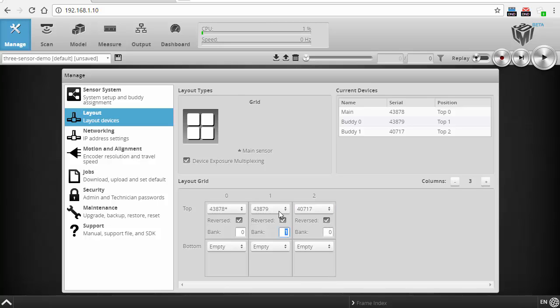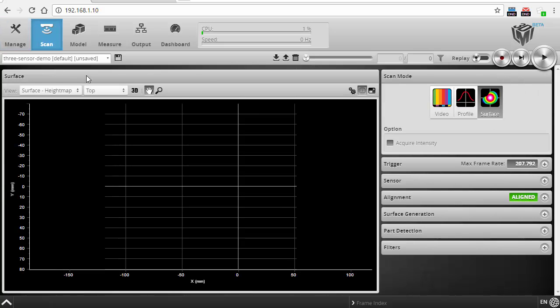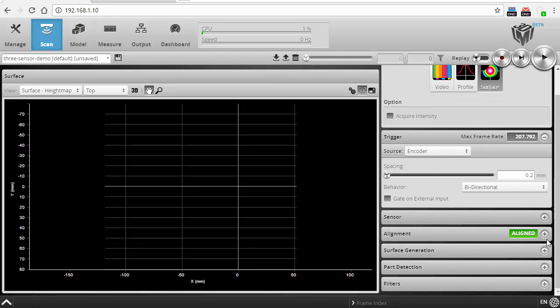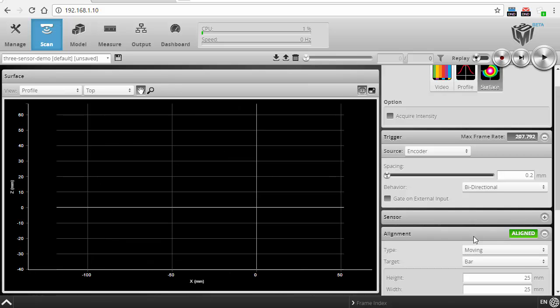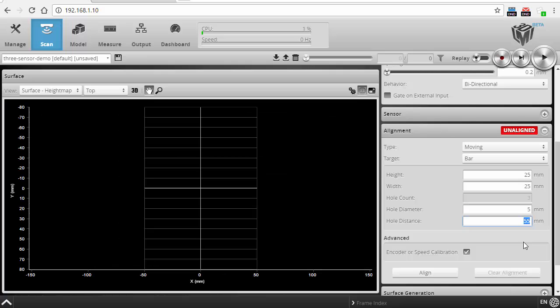So now to perform the alignment, which is the next step, all I have to do is go into the scan page. I've already got encoder set up as my input for triggering, and I then go into alignment. I'm going to clear the alignment that's in here right now. So all I have to do now is position the bar on the conveyor, and then I click the align button here.